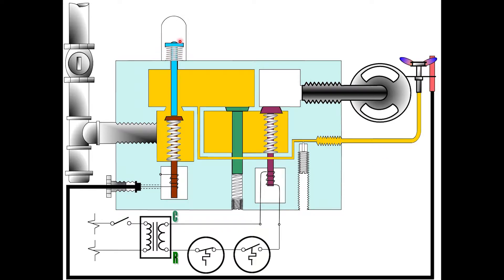So we are continuing to hold down this reset button while our thermocouple heats up. That's what's happening right now and eventually we're gonna get electricity flowing down through here to my power unit which is a little electromagnet that's gonna hold this plunger in place when we release this button here. So we release the button and this stays in the open position, that means we are good to go.